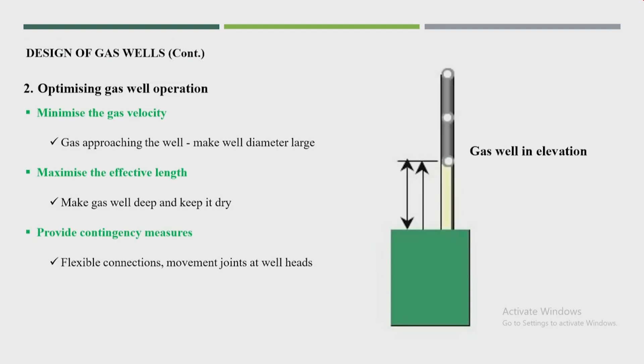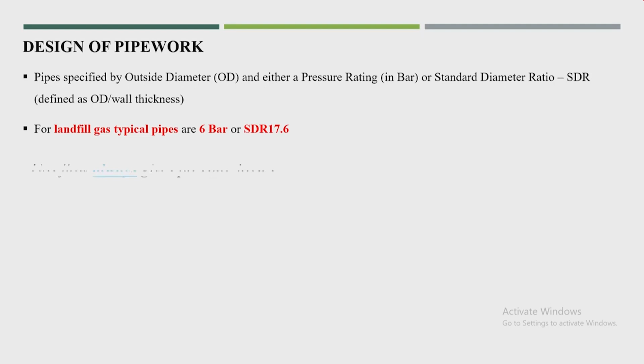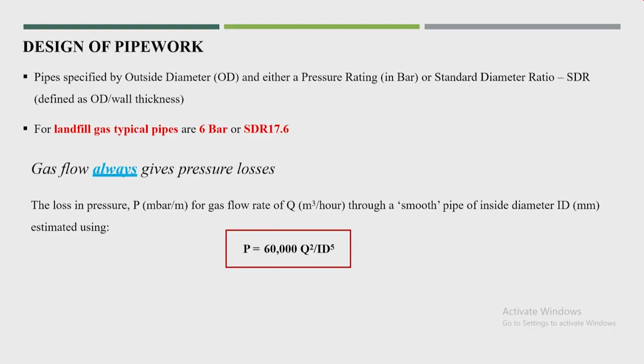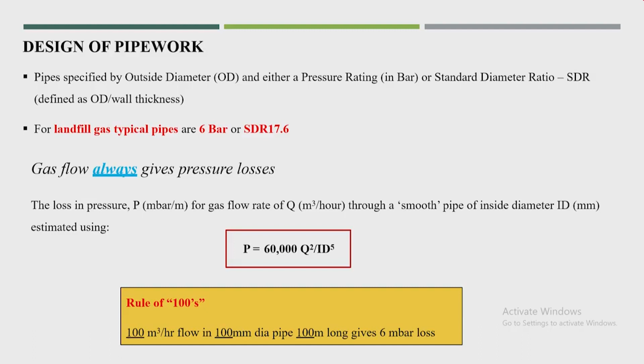Now, the design of pipe works. Pipes specify outside diameter and standard diameter. For landfill gas, typically pipes are rated 6 bar, and gas flow always gives pressure losses. The loss of pressure P for a gas flow rate of Q through a smooth pipe of inside diameter ID is estimated using P equal to 60,000 times Q squared divided by ID to the fifth. Here ID is the inside diameter of the pipe, and normally we follow a rule called the hundreds rule: 100 meter cube per hour of gas flow in a 100 mm diameter pipe, 100 m long, gives 6 millibar loss. So normally we calculate based on these basics.